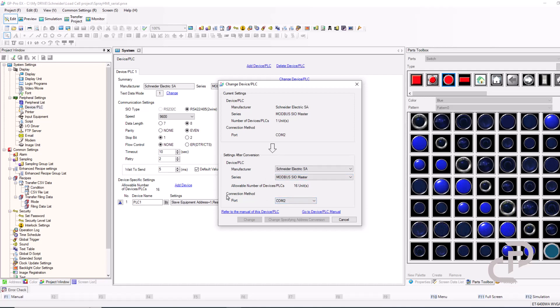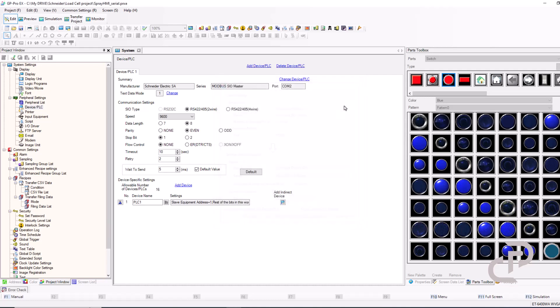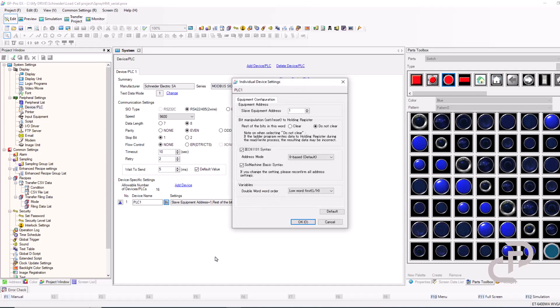RS-485 baud rate setting is 9600. Data length is 8 with even parity and one stop bit. Here in individual setting, you have to select Machine Expert Basic syntax. The slave address is 1.